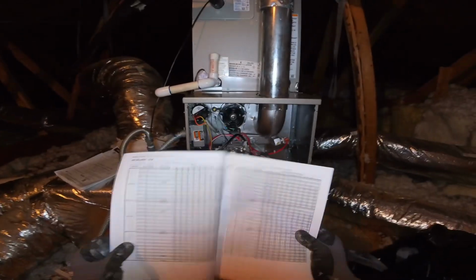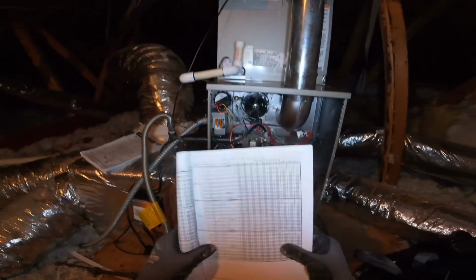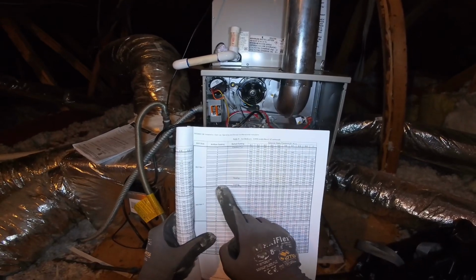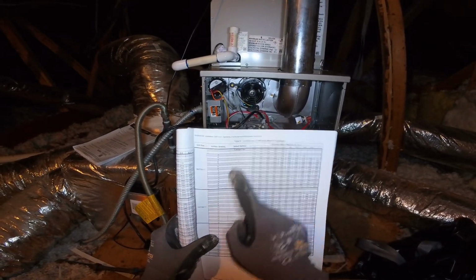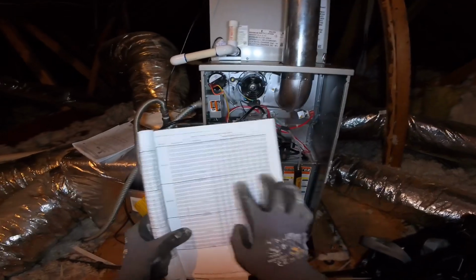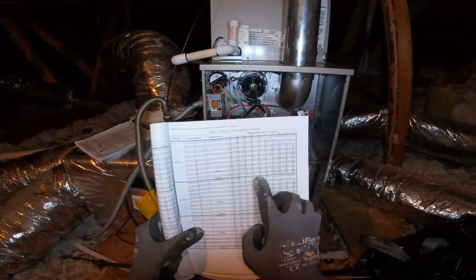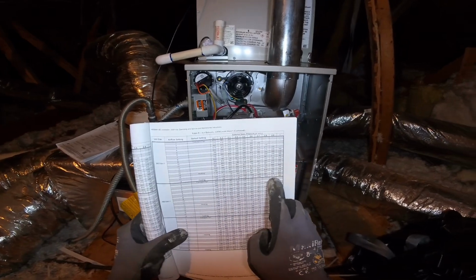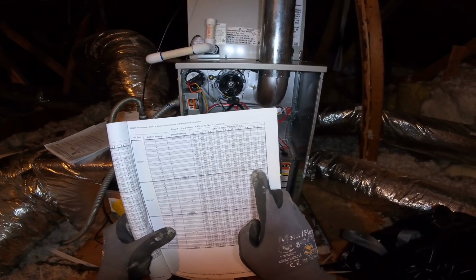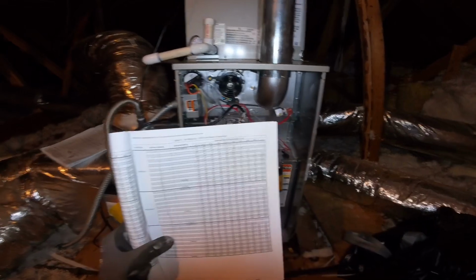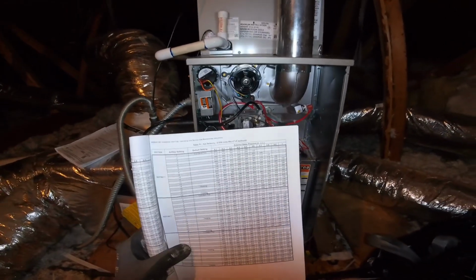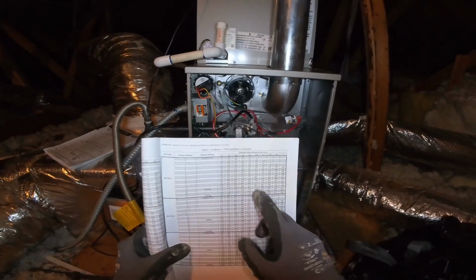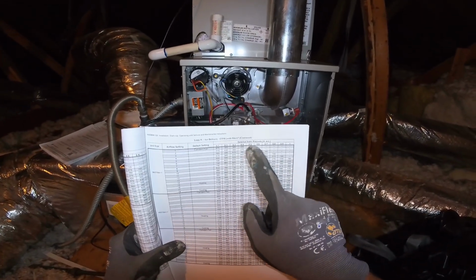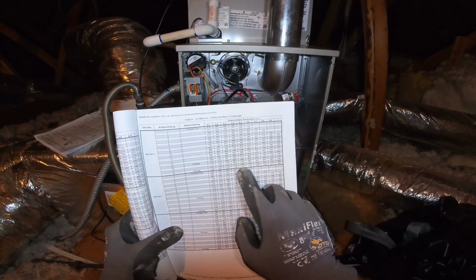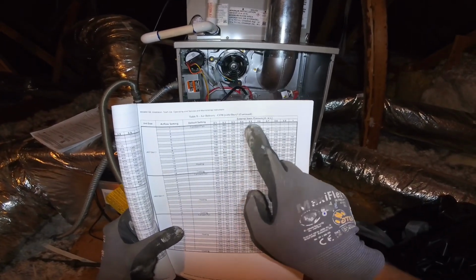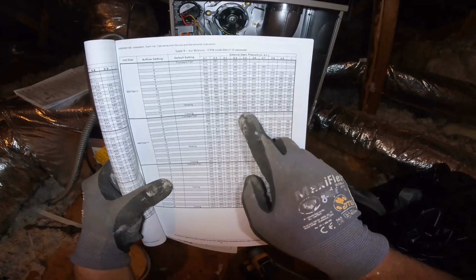Don't you just love it when you got the service manual right here? You don't have to look up the blower chart. Anyways, this is already on speed tap 18. There's 18 settings on this furnace. For the cooling, it is on speed tap 18. We are only getting 1015 CFM, so that's barely 2.5 for a 2.5. So we got to do something about the duct work. At least if I get this down to 0.5, we'll get that. We will, if I get this down to 0.5, we will get 1160.